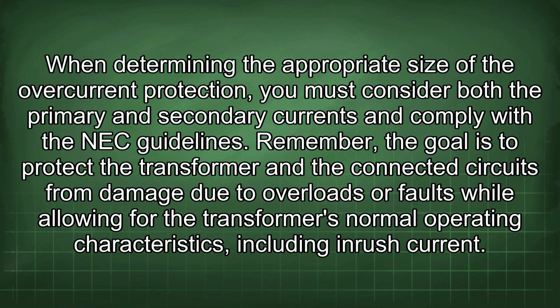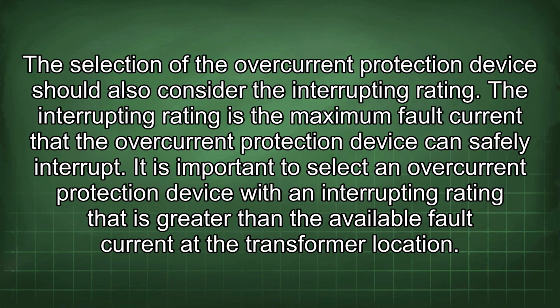When determining the appropriate size of the overcurrent protection, you must consider both the primary and secondary currents and comply with the NEC guidelines. Remember, the goal is to protect the transformer and the connected circuits from damage due to overloads or faults while allowing for the transformer's normal operating characteristics, including inrush current. The selection of the overcurrent protection device should also consider the interrupting rating.